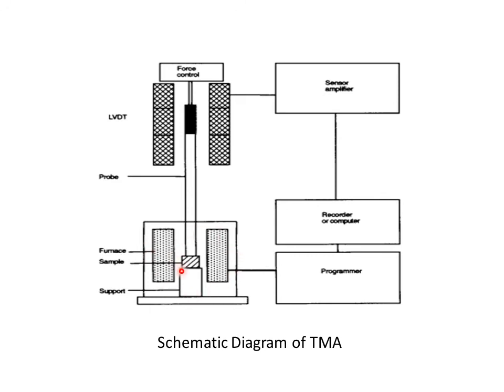So the environment can be controlled, meaning whatever type of gases you put inside, you can do it. Then here is the LVDT, which we have seen earlier. LVDT, primary coil, secondary coil system, all of them are here.